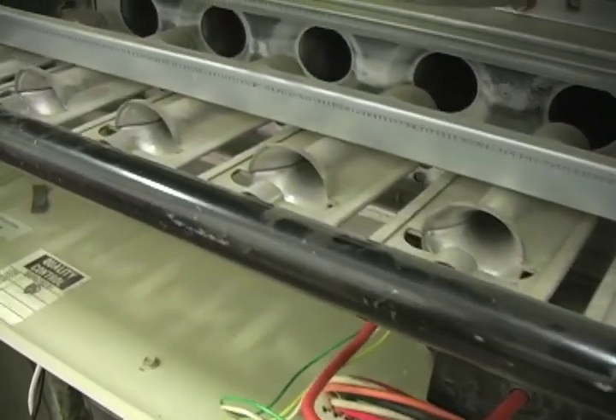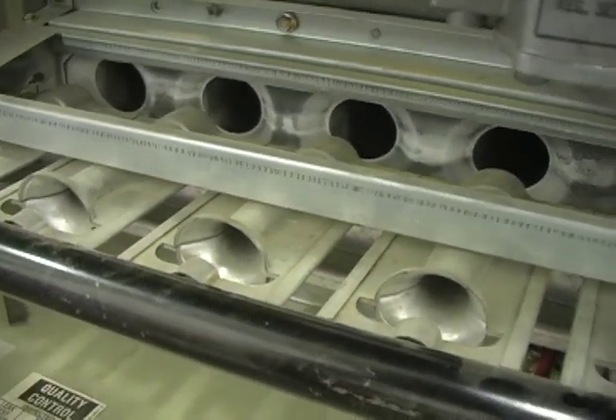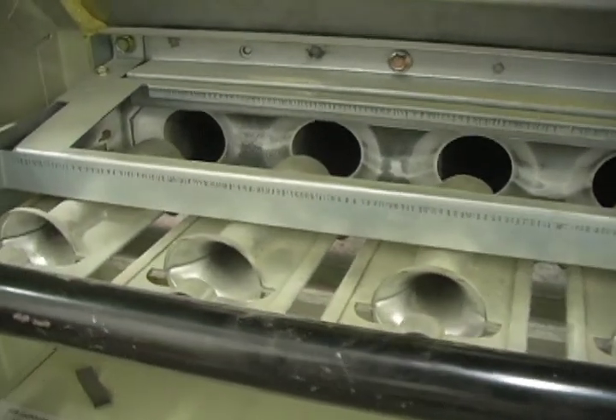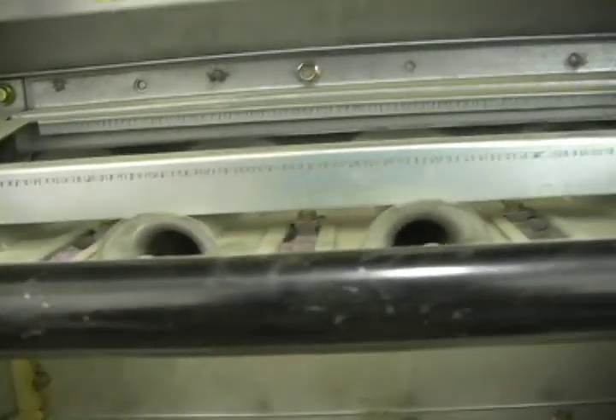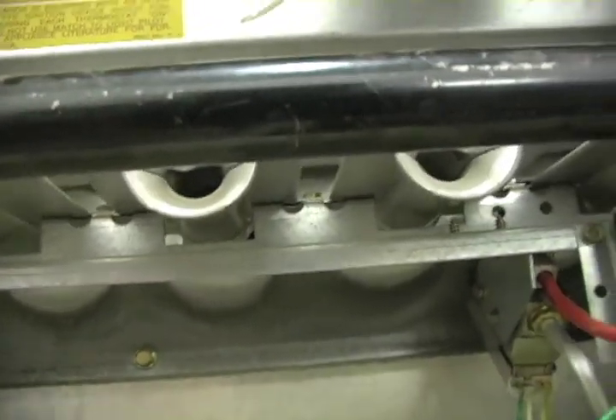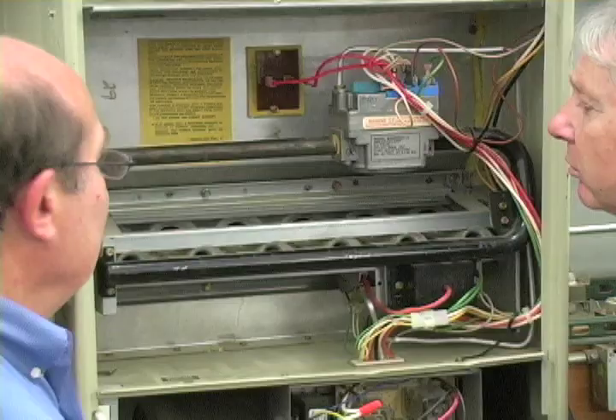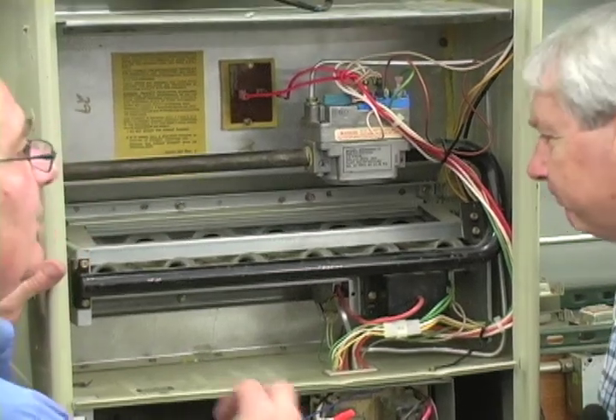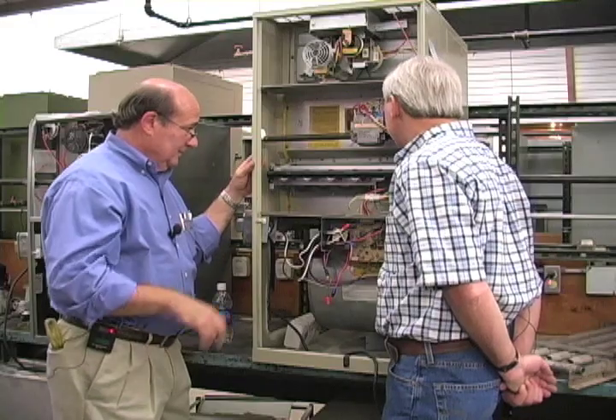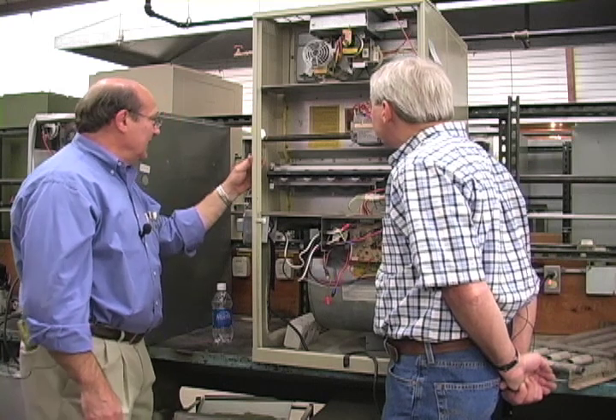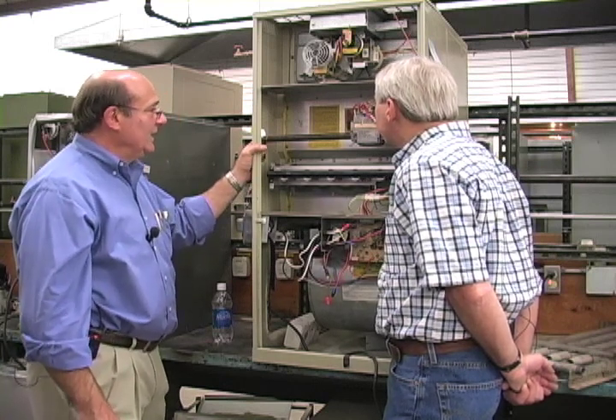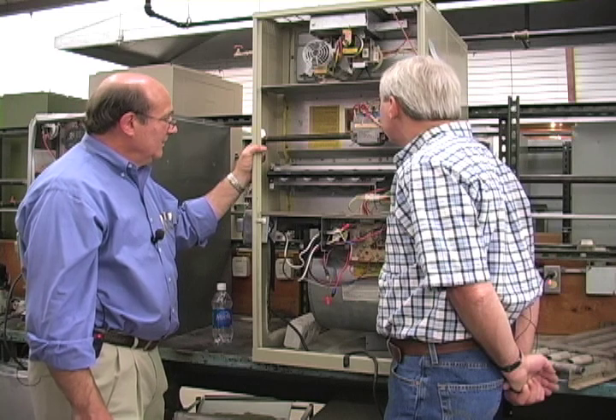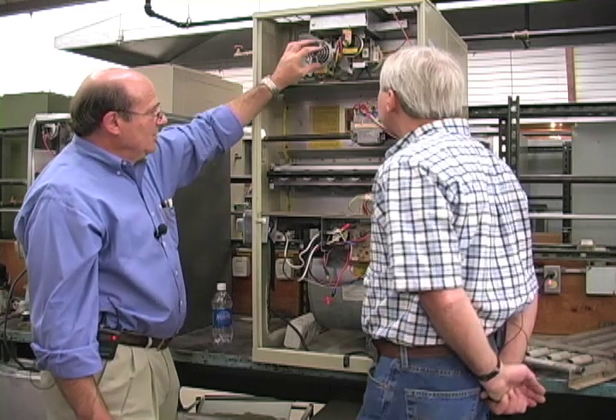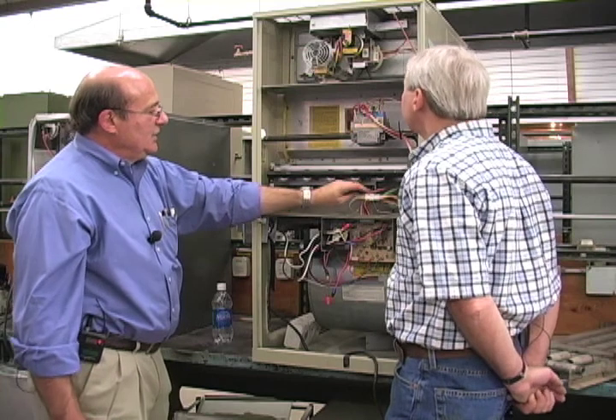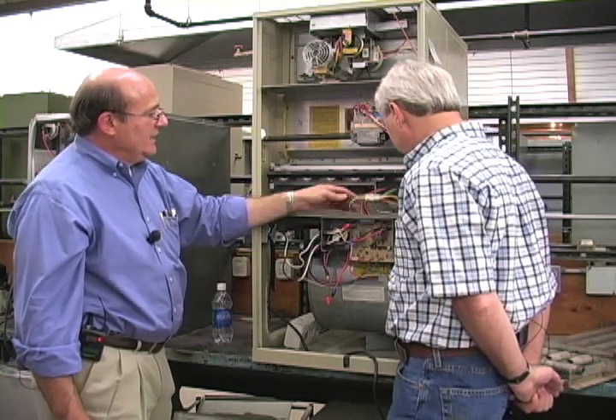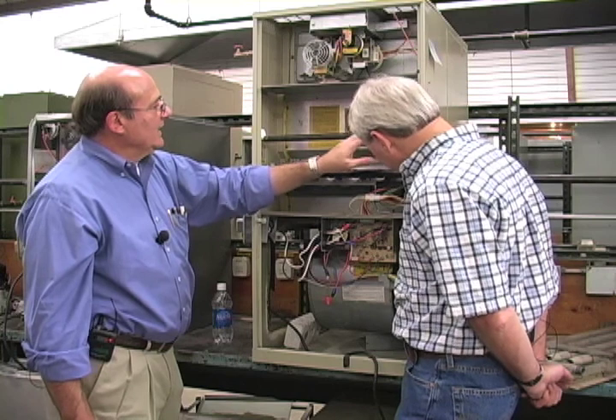That's to allow excess air to enter the combustion compartment. That's because we have all of this air we're inducing through this blower. We need to get a good shot of air in through that burner assembly, and so we have that gap there, and we actually draw the flame into the heat exchanger. Gotcha. So we can go ahead and cycle this on. Again, we don't have gas hooked up, so we're not going to get ignition on it, but at least you'll be able to see the combustion blower, the sequence. Combustion blower first, then we get ignition at our spark, we get flame sensing at the pilot light, and we get the main valve opening.